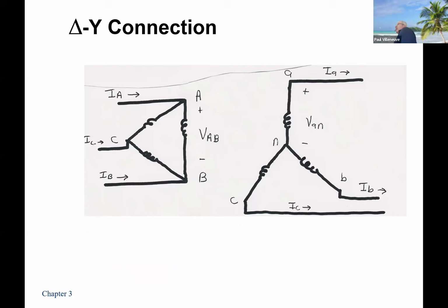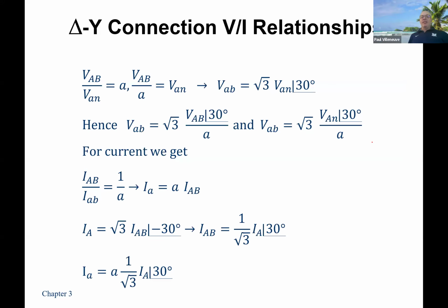Delta-Y is very commonly used in industrial facilities, because it provides what's called zero sequence filtering. But you'll notice VAB is across the winding on the high side. Then on the secondary side, VAN is here, and the actual VAB is over here. So you have a 30-degree phase shift vectorially introduced. And you also have a square root of 3, because this to this transfers by the turns ratio, but going over here, I actually have a multiplier of square root of 3. So I end up having to make some adjustments. You can see my turns ratio is adjusted here, square root of 3, and my 30 degrees in addition to the turns.